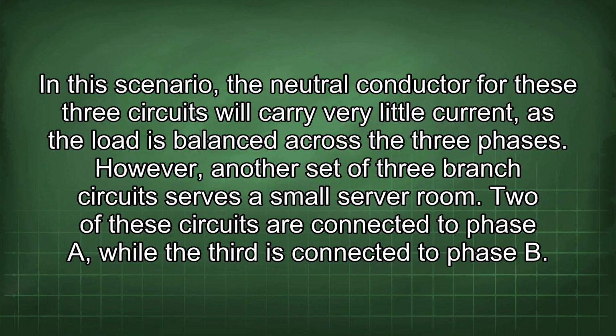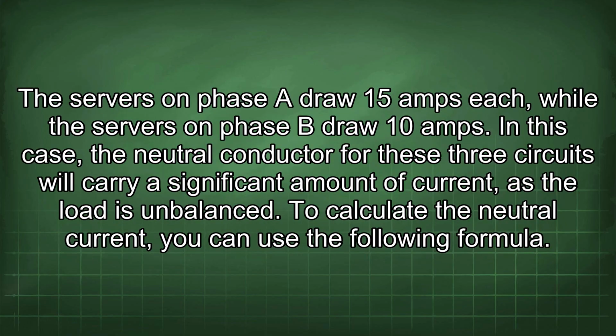However, another set of 3 branch circuits serves the small server room. 2 of these circuits are connected to phase A, while the third is connected to phase B. The servers on phase A draw 15 amps each, while the servers on phase B draw 10 amps. In this case, the neutral conductor for these three circuits will carry a significant amount of current as the load is unbalanced. To calculate the neutral current, you can use the following formula.